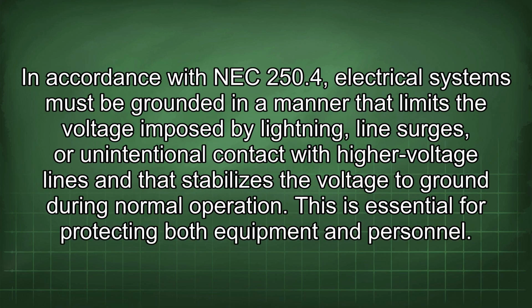In accordance with NEC 250.4, electrical systems must be grounded in a manner that limits the voltage imposed by lightning, line surges, or unintentional contact with higher voltage lines, and that stabilizes the voltage to ground during normal operation. This is essential for protecting both equipment and personnel.